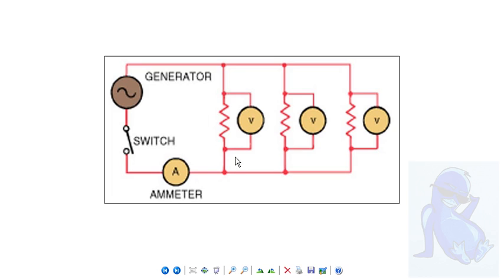How many calculations you're actually going to have to do varies. I haven't had to do that nearly so much. It's important that you understand, though, this parallel circuit, and that's what you're going to be working with the most. You're going to take amp meters in series, and typically your multimeter is going to have a clamp. You're going to clamp it around that wire while the system is running. You're going to take an amp reading.